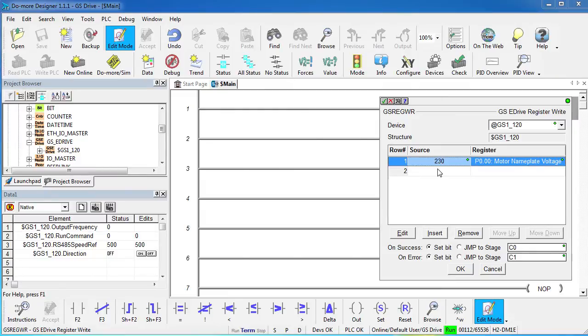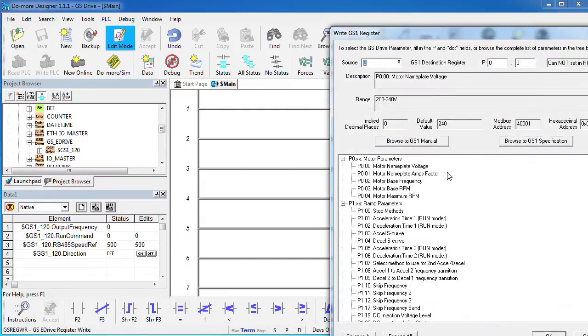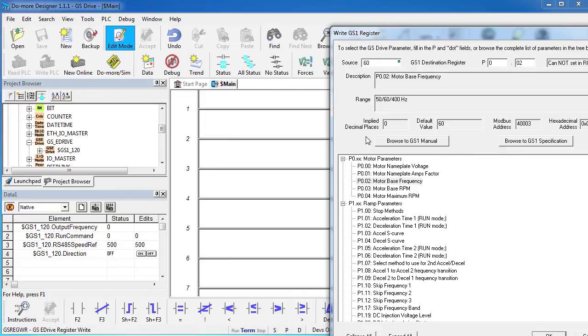Let's do another parameter – double click on the row – and I want to do the motor base frequency. Well, I can see that's 50, 60 or 400 Hz – I know I want mine to be 60 Hz. That's going to go into parameter 2 – it's the motor base frequency – there are no implied decimal places – that's good – and my default value is 60 – great.